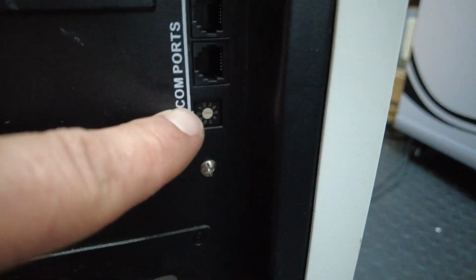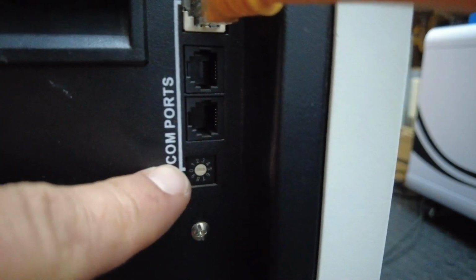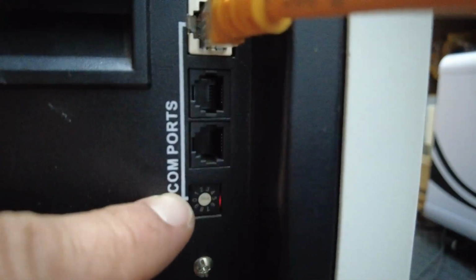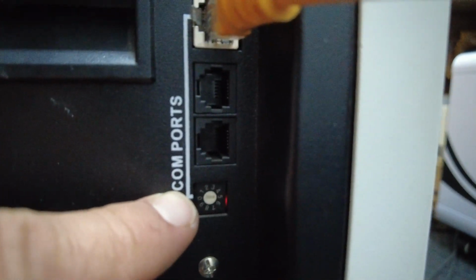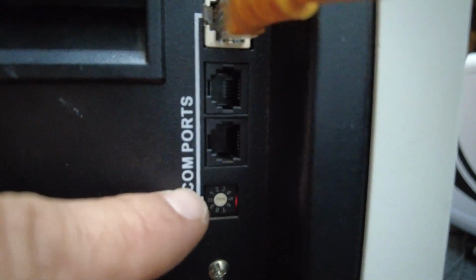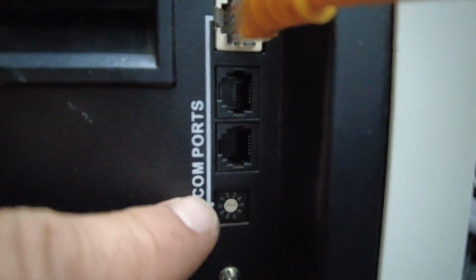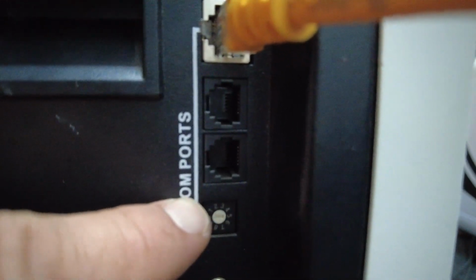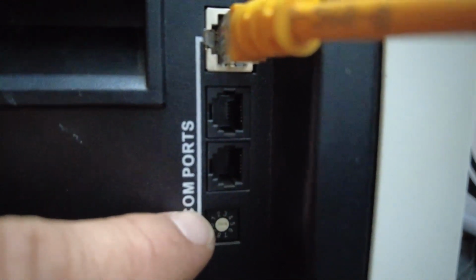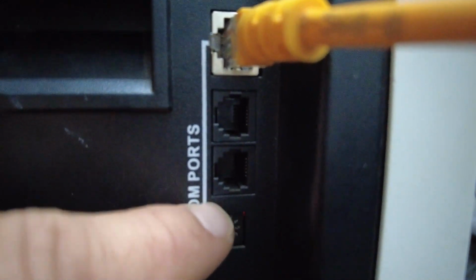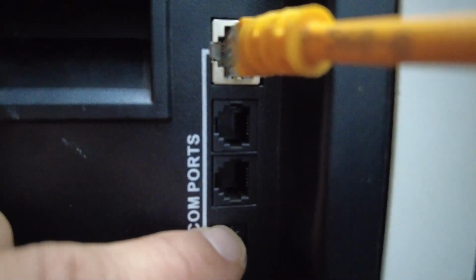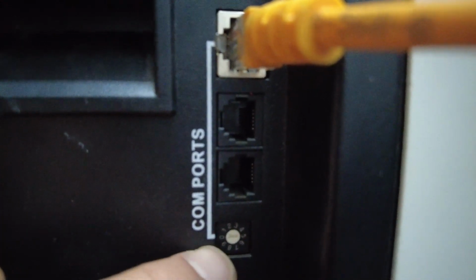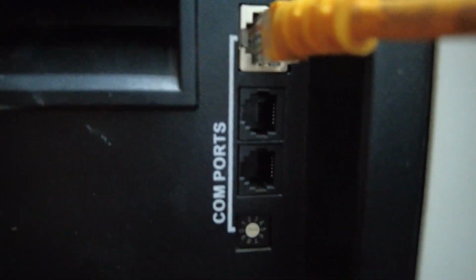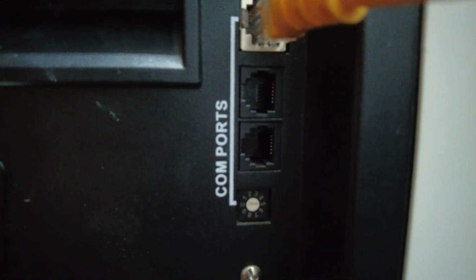Something I can recommend: dip number 0 on this dial is set for your master. Master is always set to 0. Your second battery will be set to number 1. The next battery will be number 2, and so on up to 9, which is the maximum amount of batteries you can connect.